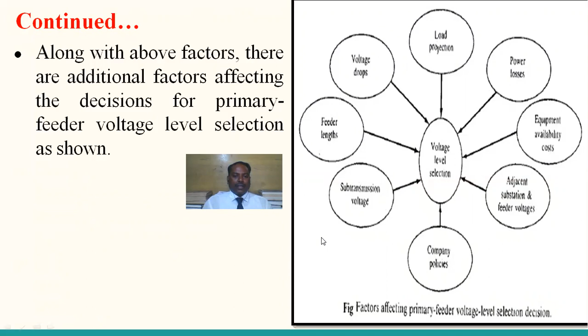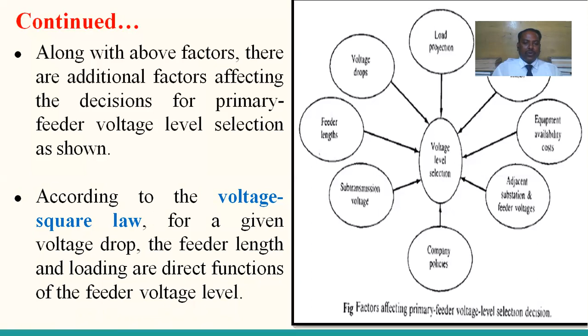And as per the voltage square law, what the voltage square law gives us is that for a given voltage drop, the feeder length and loading are direct functions of the feeder voltage level. Very clear. What the voltage square law informs is that the given voltage drop is the main concern to be considered. For a given voltage drop, the feeder length as well as loading are direct functions of the feeder voltage level.